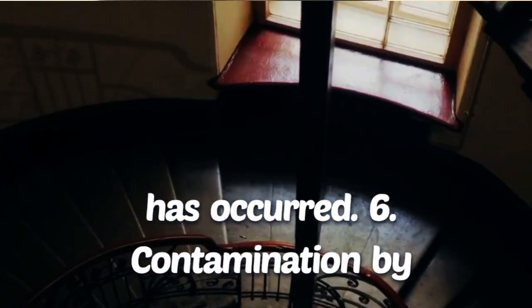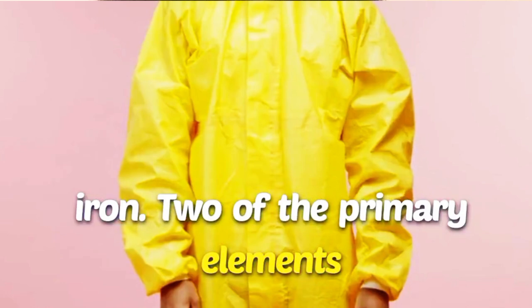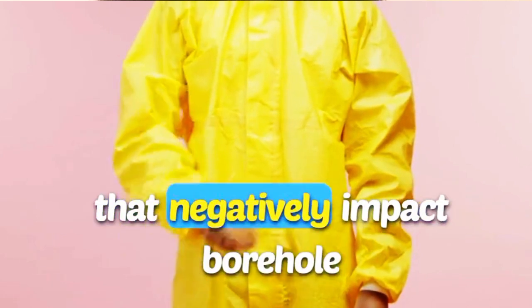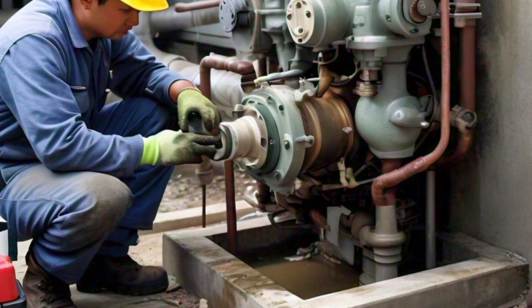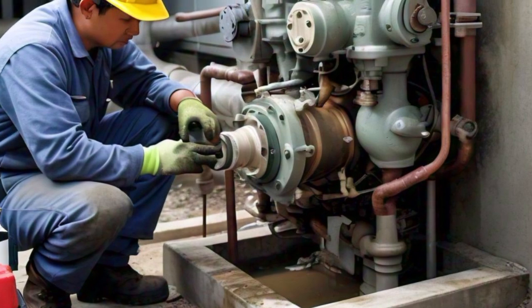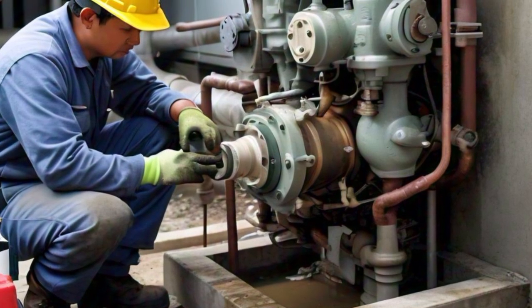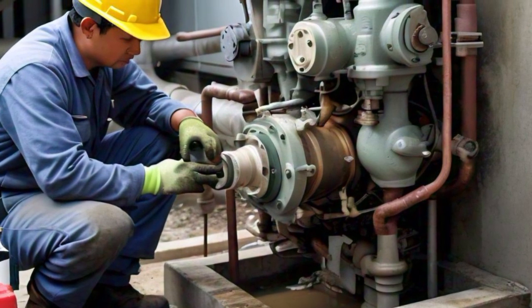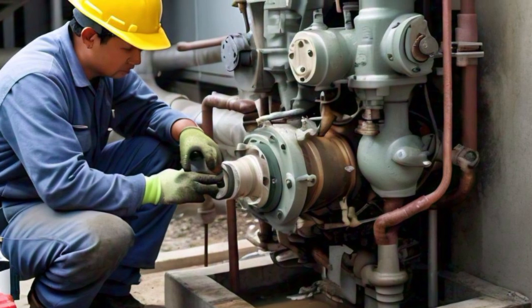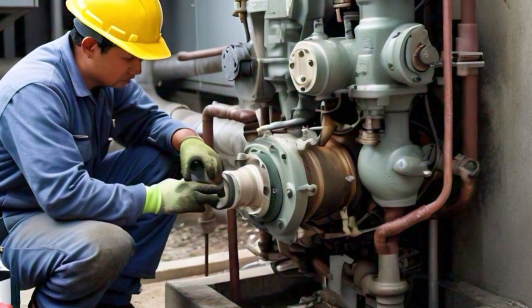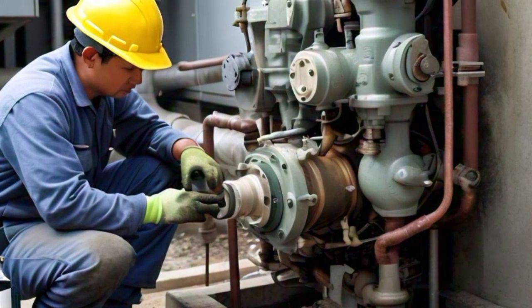6. Contamination by iron. Two of the primary elements that negatively impact borehole pumps are iron oxidation and iron bacteria. These impurities build up and cause the pump's components to clog and corrode, which may ultimately result in total system failure.